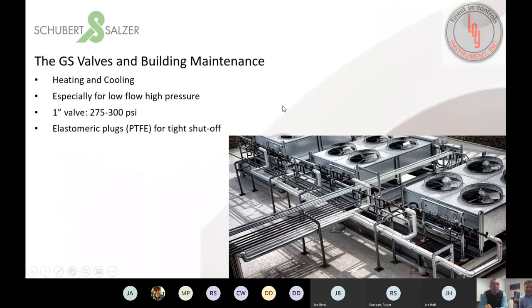So when I say building maintenance here, I'm talking about utilities. Here's the GS valve. We use it a lot in HVAC. Actually, this is not a picture. I didn't have a picture with the valve on it, but we have used them in several places with utilities. So heating or cooling, chilled water, steam, glycol, especially if you're talking about low flow and high pressure, a lot of the cheaper HVAC valves cannot handle the high pressure, whereas ours, a 1-inch, for example, would handle easily 275 to 300 PSI. And again, you can use the elastomeric plugs, like the PTFE or the...